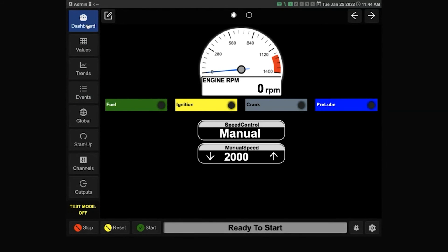So if you've implemented a new custom fault condition and the package goes down based on one of those custom faults, you can see over Modbus that the fault condition was number 23 or number 14 or whatever fault code you've assigned in your custom script, and then you can build a table on the other end to receive that Modbus data, and then display the reason for the shutdown.